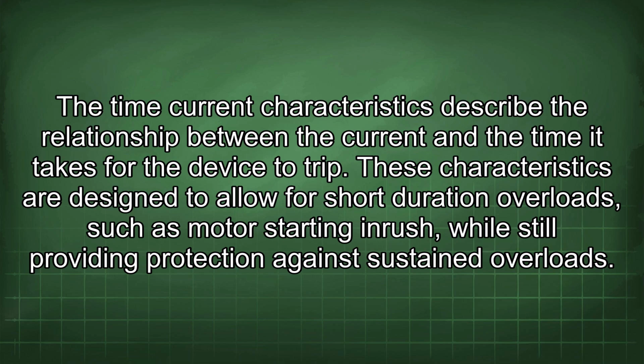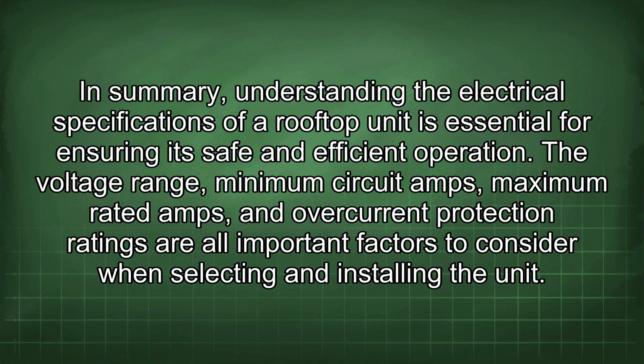These characteristics are designed to allow for short duration overloads, such as motor starting inrush, while still providing protection against sustained overloads. In summary, understanding the electrical specifications of a rooftop unit is essential for ensuring its safe and efficient operation. The voltage range, minimum circuit amps, maximum rated amps, and overcurrent protection ratings are all important factors to consider when selecting and installing the unit.